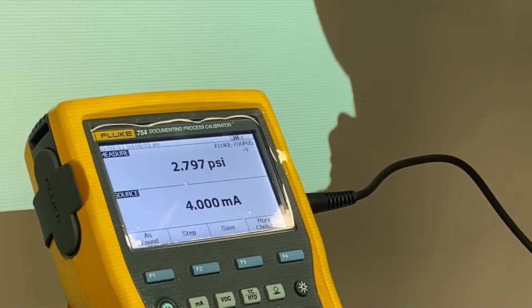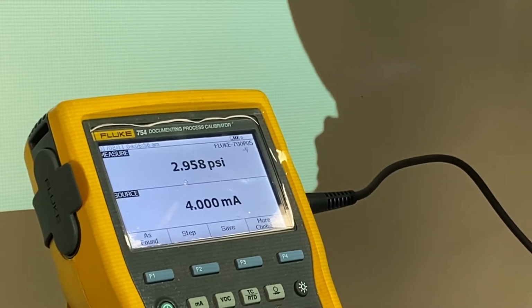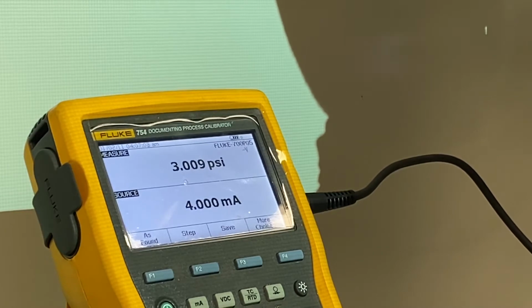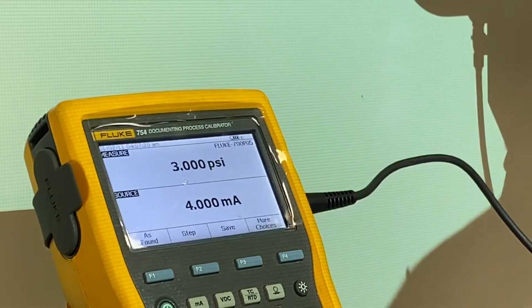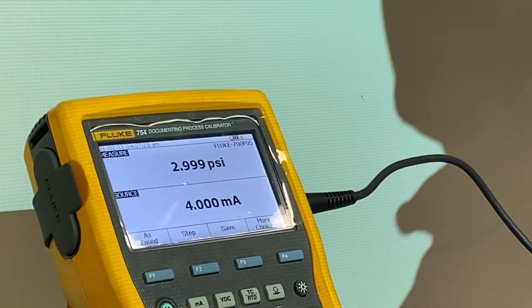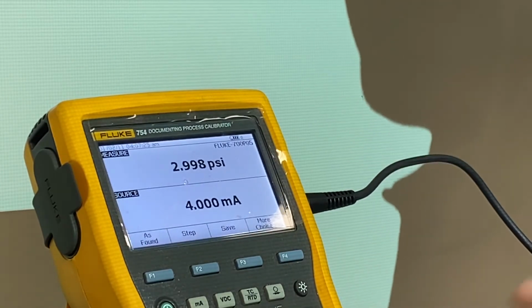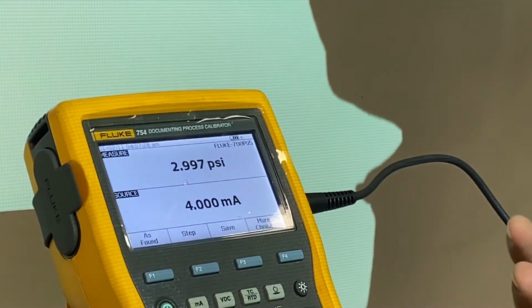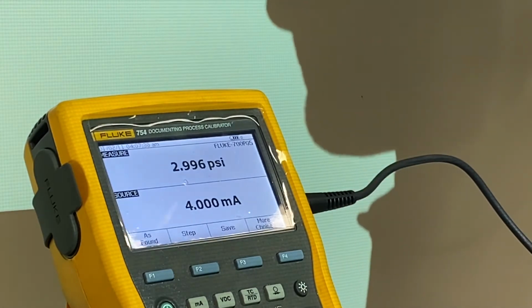And once we get it in close, we can move a little slower so we don't overshoot. And as that stands, we are well within tolerance. So now we're going to check it at our upper range value of 20 milliamps. We should be outputting 15 psi.